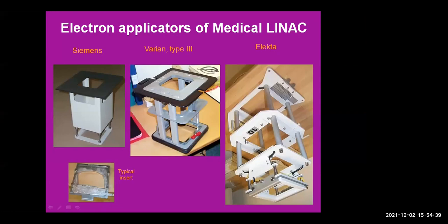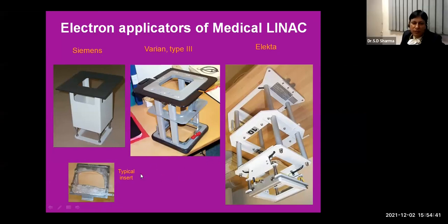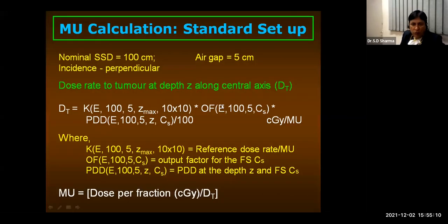So these are the different applicators of different vendors. One important thing I wanted to bring to your knowledge is that the applicators or field size projected by the cones are not sufficient for treating the patient. Sometimes we need to put inserts as well. So we have to find out the insert factor also while calculating monitor unit. Secondly, in case of electrons, the treatment setups are only SSD. There is no scope of SAD setup, and the reasons are known to all of you.